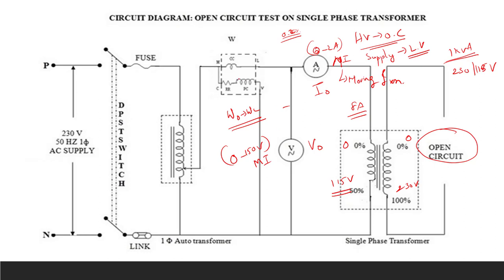We will use a wattmeter to measure the power. Since the load is zero, the current is very small, so we go for a low power factor (LPF) wattmeter. This autotransformer, also called a single-phase static device, is used to set the rated voltage for the experiment.